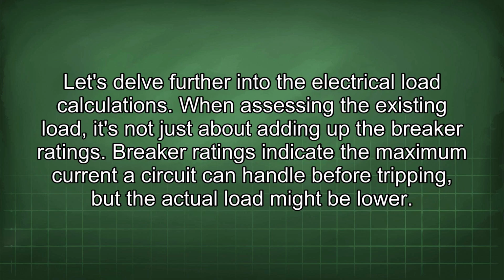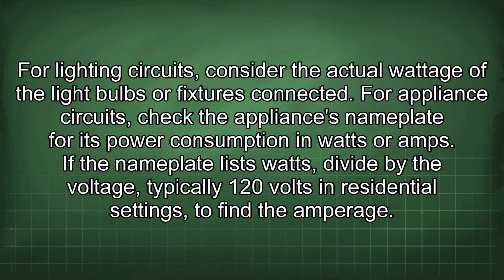Let's delve further into the electrical load calculations. When assessing the existing load, it's not just about adding up the breaker ratings. Breaker ratings indicate the maximum current a circuit can handle before tripping, but the actual load might be lower. For lighting circuits, consider the actual wattage of the light bulbs or fixtures connected. For appliance circuits, check the appliance's nameplate for its power consumption in watts or amps.